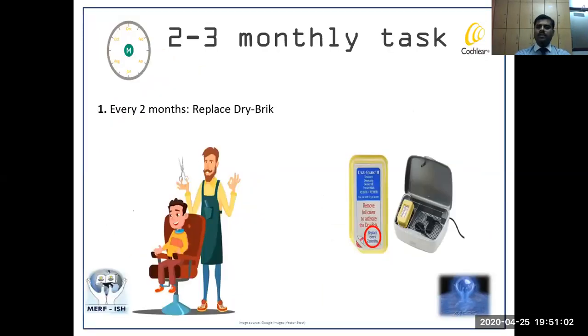Now, once every quarter, there's something very important our patients often forget - changing the Dry-Brik. This brick's life is not more than 2 to 3 months, maximum. So it's advisable to change it once every 2 months. Every time you put in a new brick, write the date on it using a marker or pen. You have 2 months from that installation date, after which you may have to change the brick. So before 2 months are up, if you're running low, order more from the company or clinic and keep extra stock.